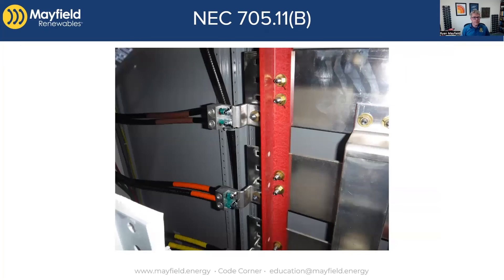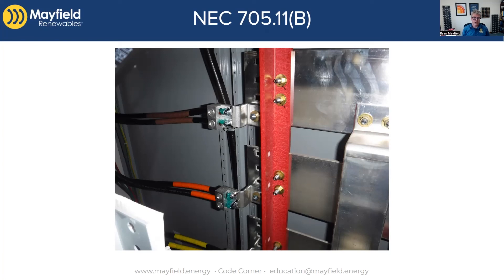And then 705.11b — here's an image showing some conductors that are obviously larger than 6 AWG, parallel runs greater than one per other code rules. Just an image showing that we have to have our conductors properly sized. We're going to talk in a future CodeCorner about these connections, their ratings, field listing, and all that. But making sure your conductors are large enough to meet that code requirement is the key takeaway.